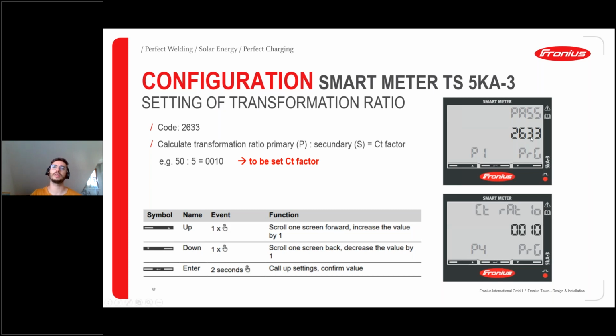When entering the password, we go to page 4 with the up and down buttons, where it states current ratio. There we need to set the correct ratio of our current transducers. For example, in our case we have a calculated transformation ratio from primary to secondary of 50 to 5, which is 10, so we need to set 0010. Then we press enter again, leave this page, and we're set and ready to go.